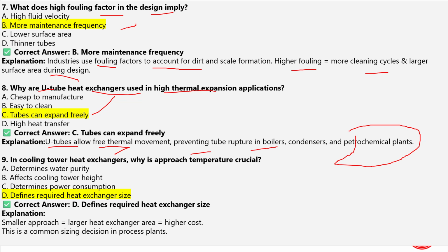Moving on to the last question of today's video. In cooling tower heat exchangers, why is the approach temperature crucial? A very important question. Approach temperature is crucial because it defines the required heat exchanger size. So smaller approach means larger heat exchanger area, which equals higher cost. This is a very common sizing decision in process plants, so you should be aware of it whenever we are buying a heat exchanger. We always discuss this approach temperature.